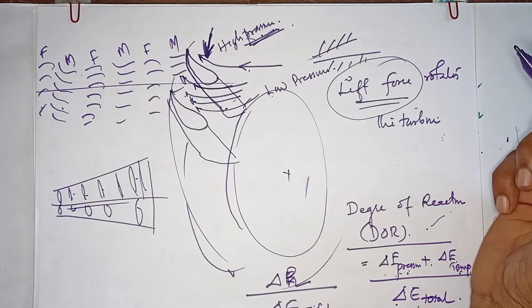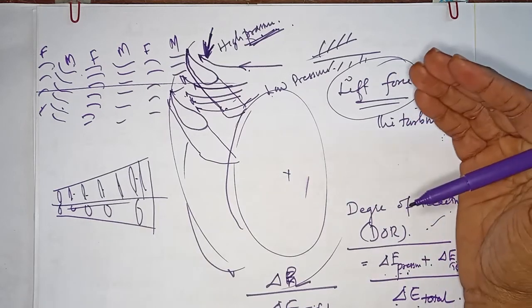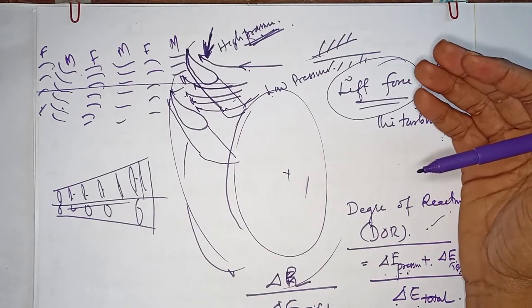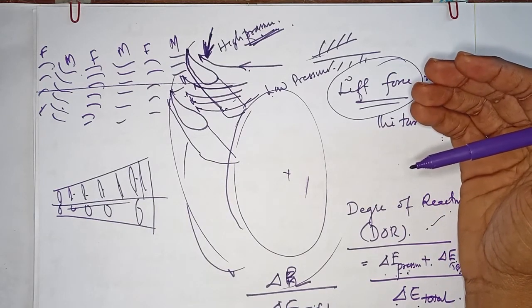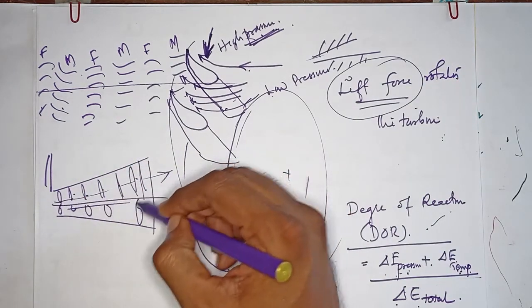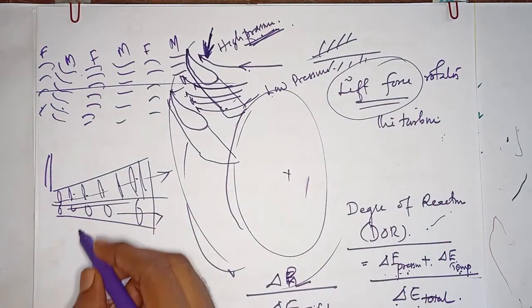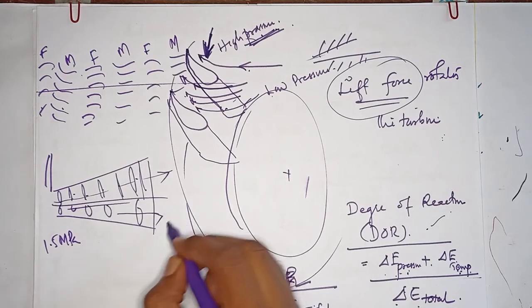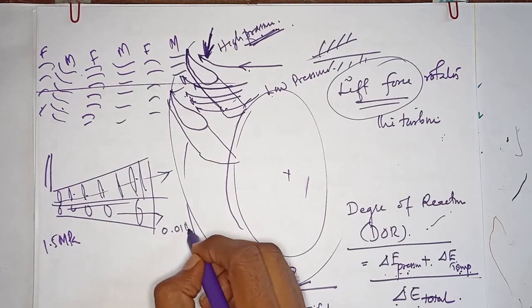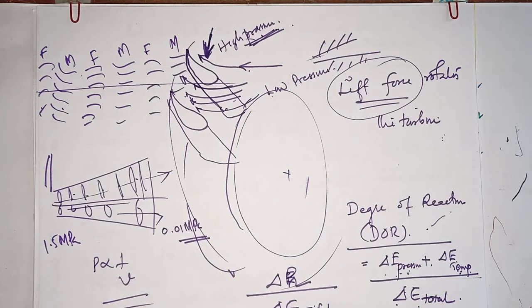As we go through the stages, there is a drastic pressure drop. The steam enters at high pressure and high temperature. For example, if the pressure is 1.5 MPa at entry, it may drop to 0.01 MPa at the exhaust. So the pressure drops significantly as the steam passes through successive stages.